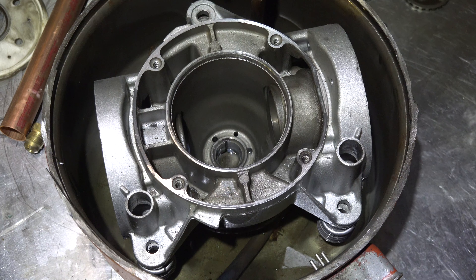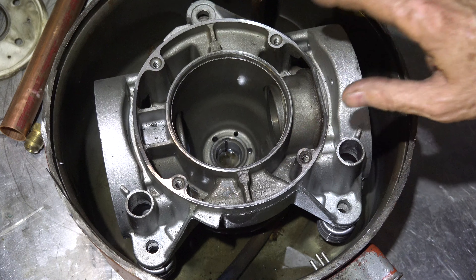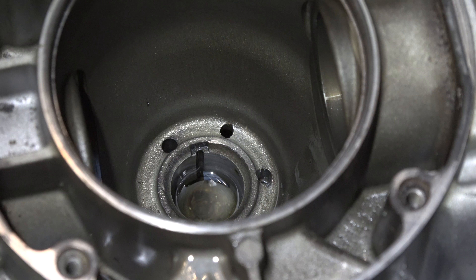This thing had a locked rotor and the locked rotor was the main bearing on the crankshaft. So why did it lock? Here's our crankcase right here, put back into the compressor can. If you look down there you can see the oil level — it's about halfway through this main bearing here.